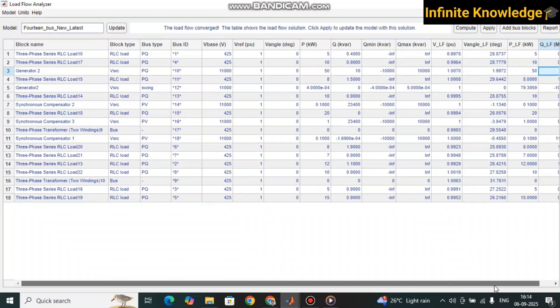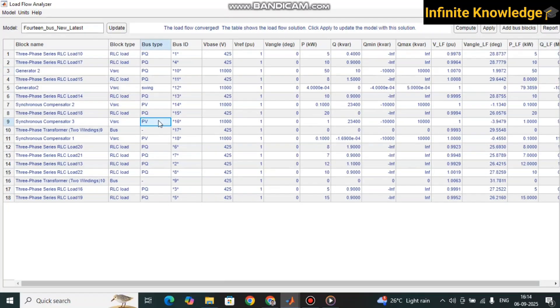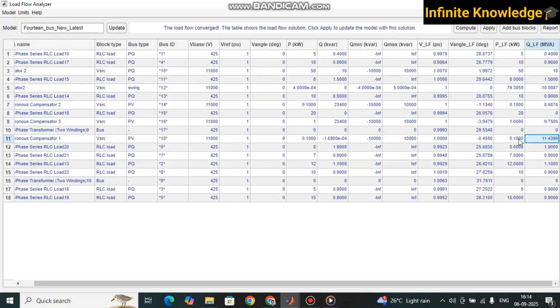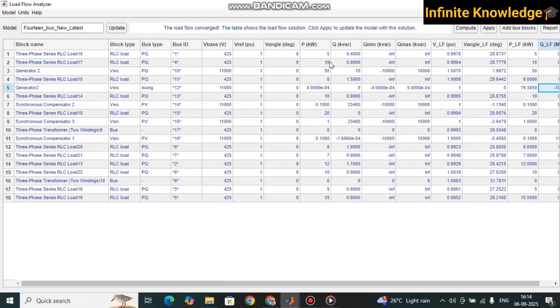For reactive power, when the bus is a PV bus or synchronous compensator, the active power is very low but it is feeding reactive power. A negative reactive power value means the bus is absorbing reactive power from the system. This is how the system works and how you can perform load flow analysis.